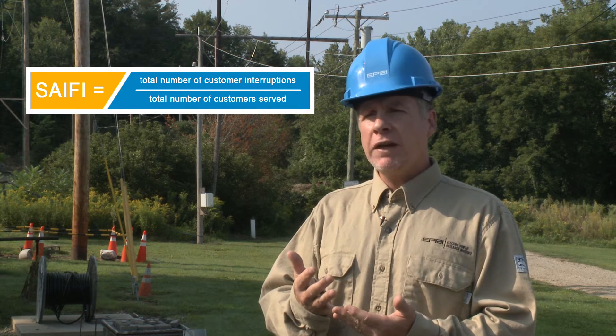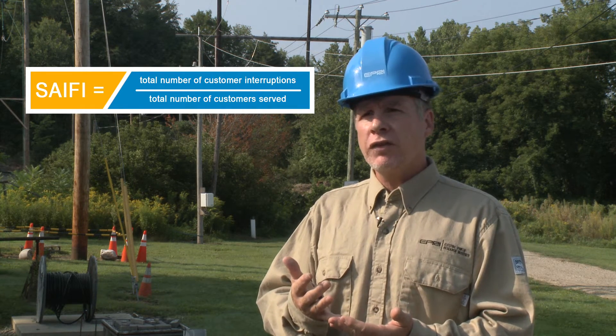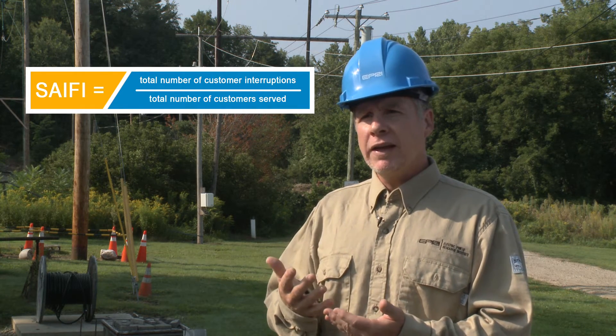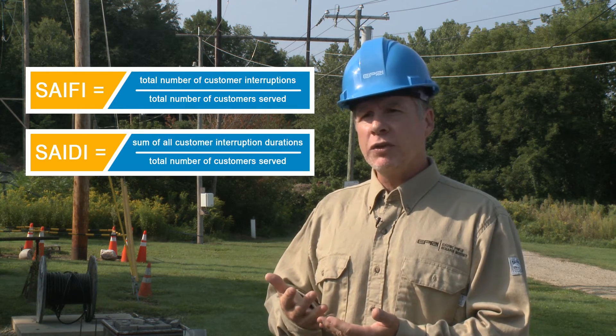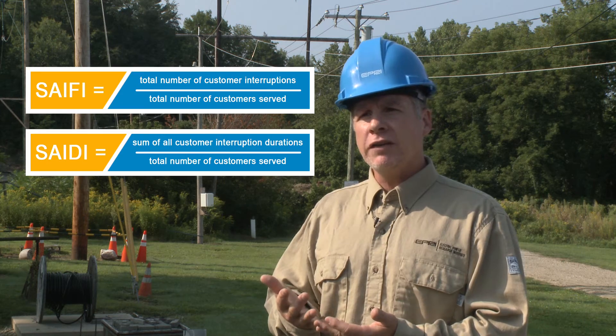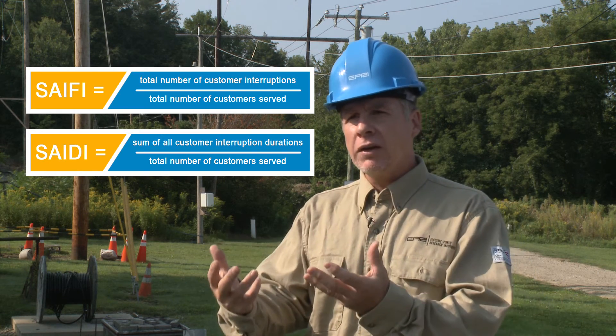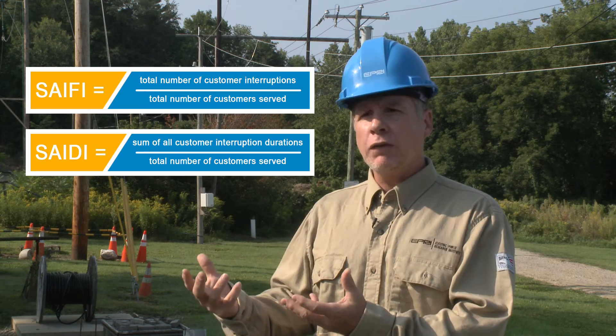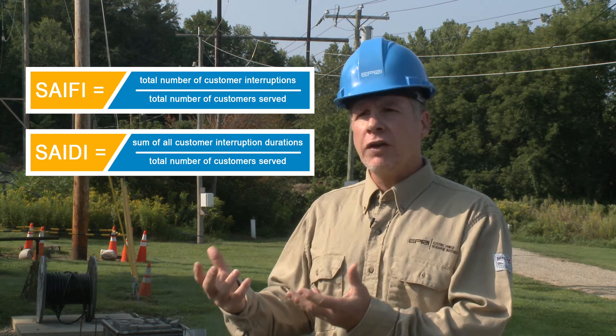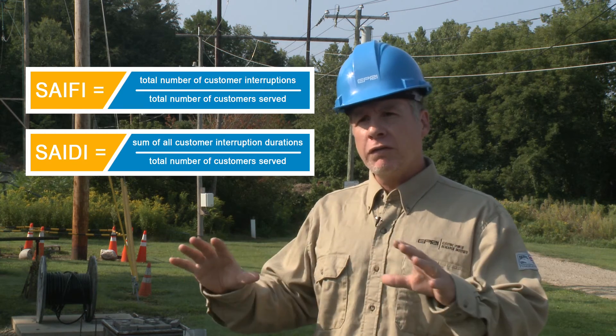We start out with a circuit without any distribution automation switches and look at the reliability indices called SAIFI, which is a frequency index on reliability, and SAIDI, which is a duration index on reliability. We calculate the predicted SAIFI and SAIDI for these feeders based on their configurations and their failure probabilities.